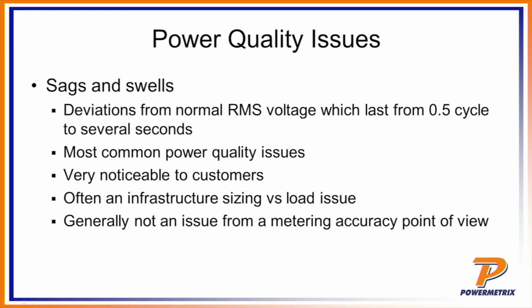When I say deviation, a sag is actually going to be a reduction in voltage. If we're talking about normal residential service, say 120 volts, that may go down quite a bit below that, or a swell, meaning that we have a voltage that goes up above that. We mentioned that can last anywhere from half a cycle. Now mind you, half a cycle meaning half of a 60 hertz cycle. A 60 hertz cycle is equivalent to about 16 milliseconds. That's 16 thousandths of a second. So half a cycle would be roughly 8 milliseconds. So we're not talking about a terribly long amount of time. In the world of modern electronics, that's a long time, but in human time, that's a very short time. Half a cycle to several seconds.